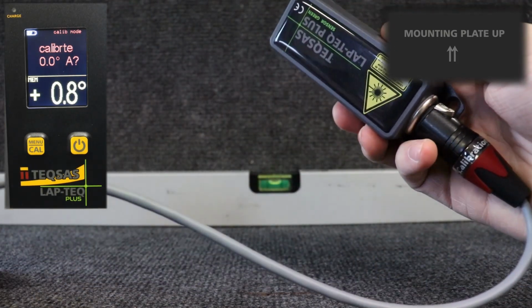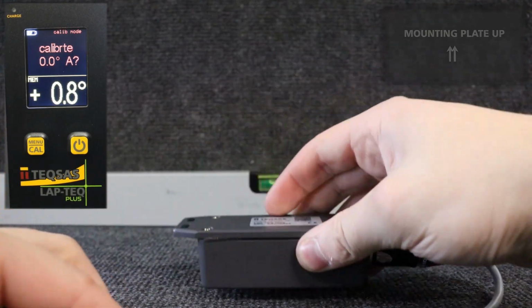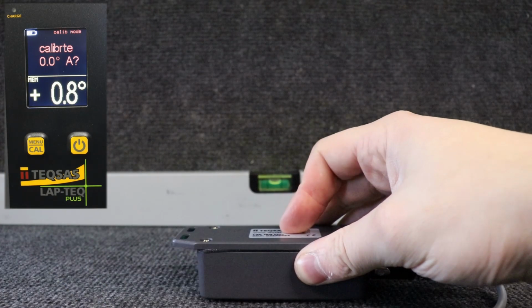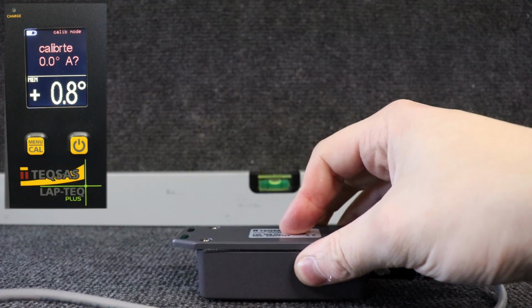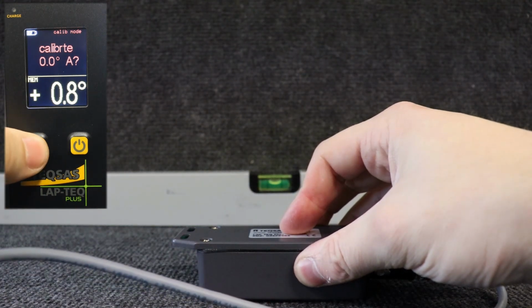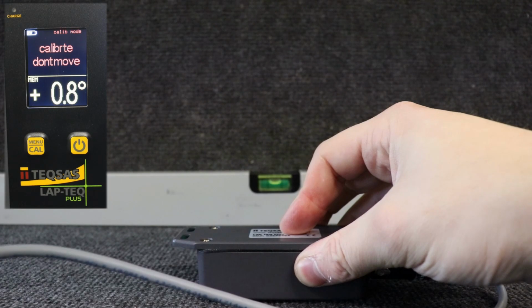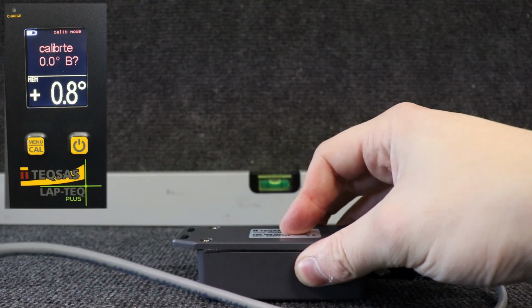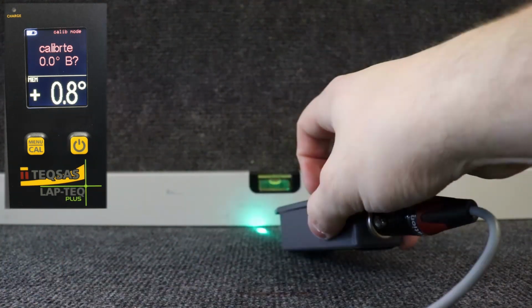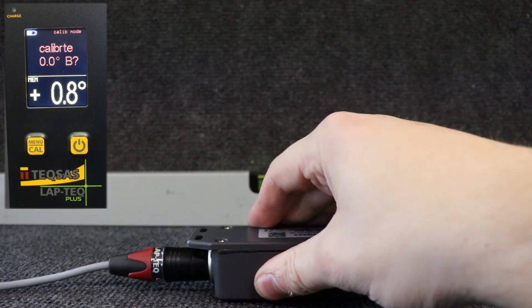Second calibration cycle is for mounting plate up. We must repeat the same 4 steps as before, but this time with the sensor upside down. First position is the sensor horizontal at precise 0.0 degrees. Second position is the sensor at 0.0 degrees pointing the opposite direction.